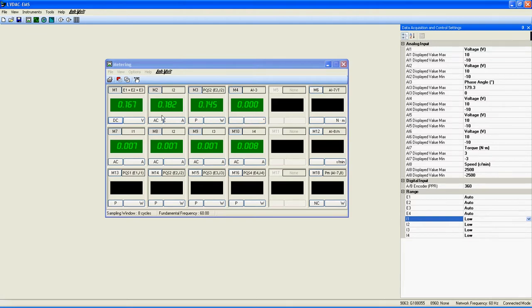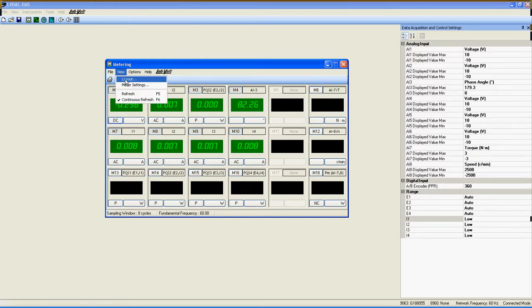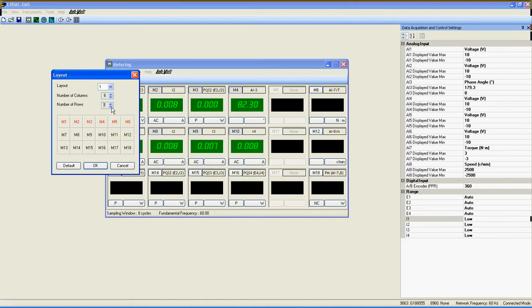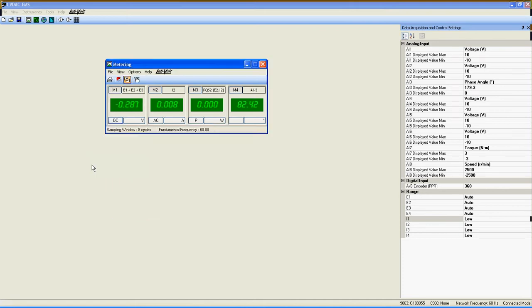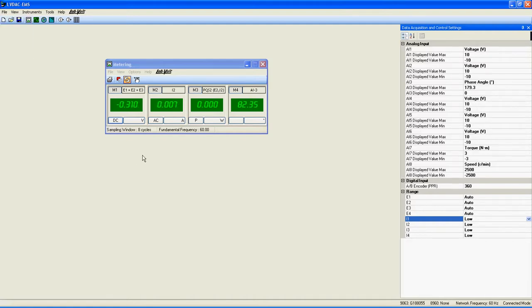We now have 4 meters ready to be used. Just click on the continuous refresh button here, and they will automatically start to show some values if the specified inputs are all correctly connected. Since the other meters are not used, you can limit the layout to reduce the space used by the metering function window. To do so, click on View, then on Layout, and adjust the number of rows and columns you want to keep displayed. Finally, you can save your settings at any time by clicking on File, then on Save As.